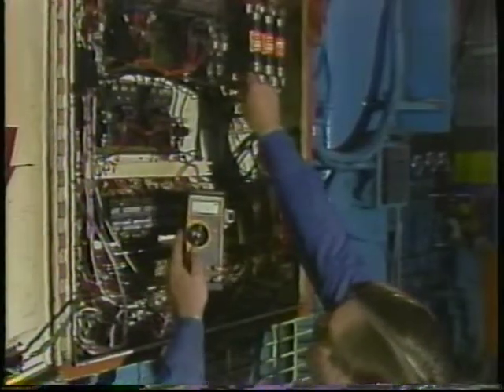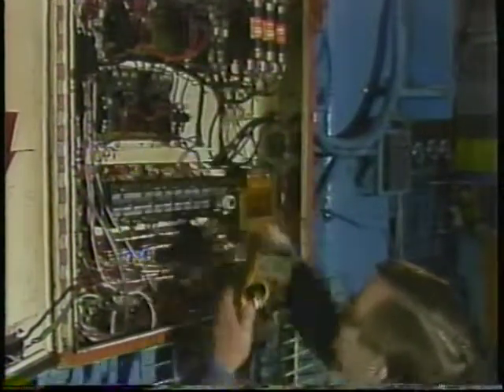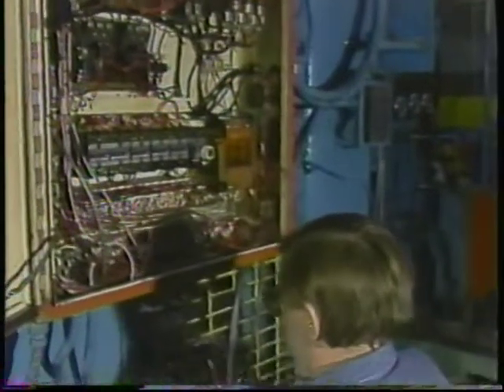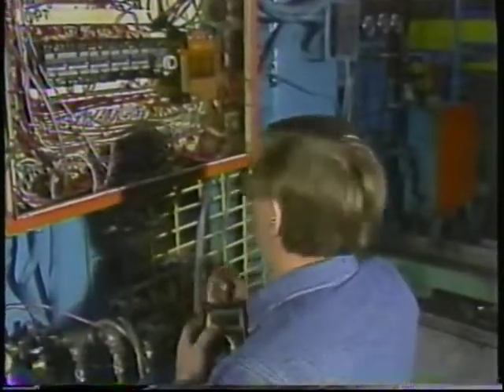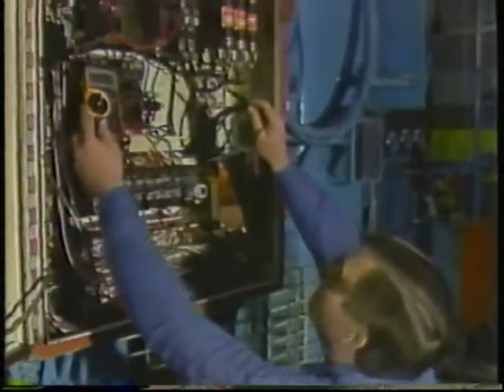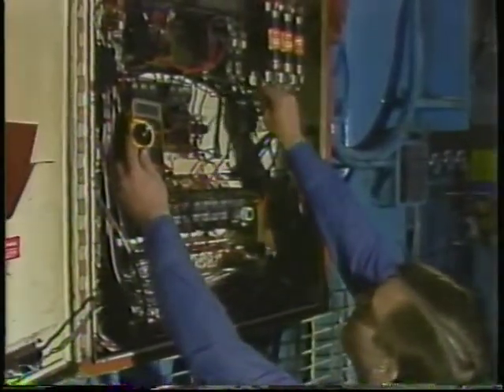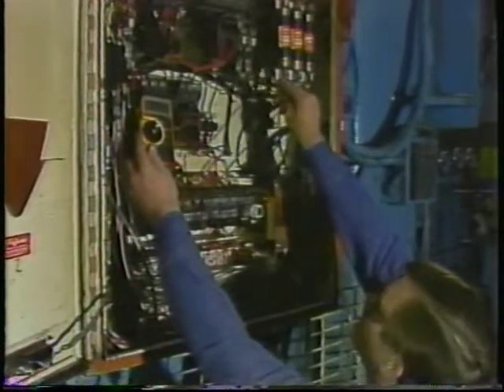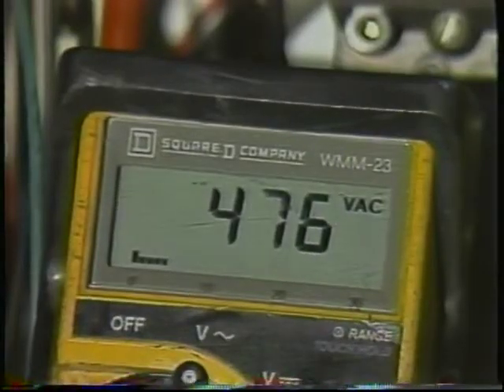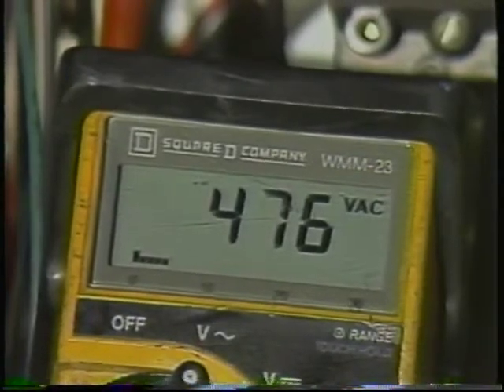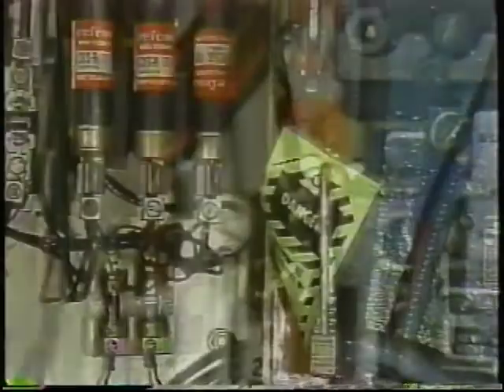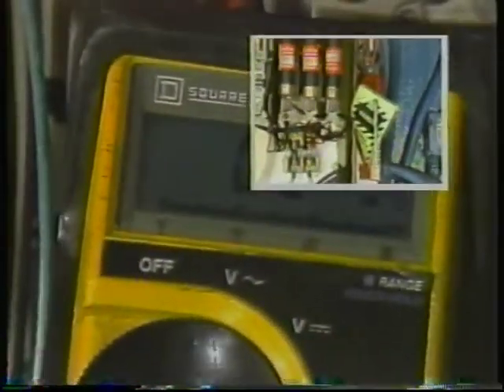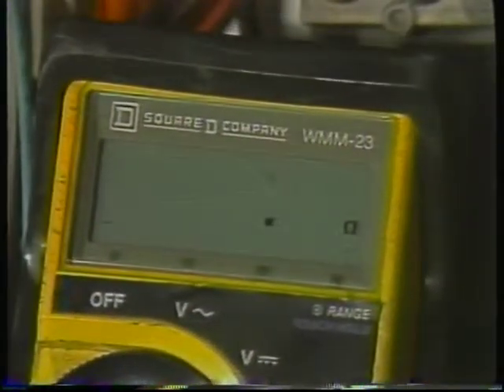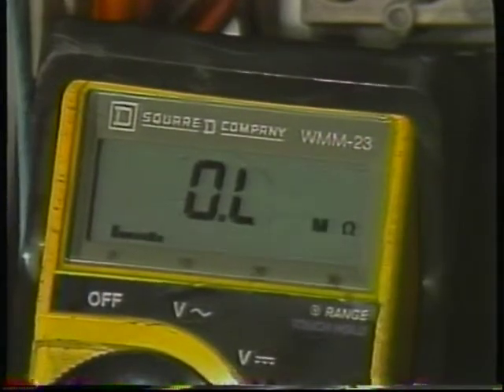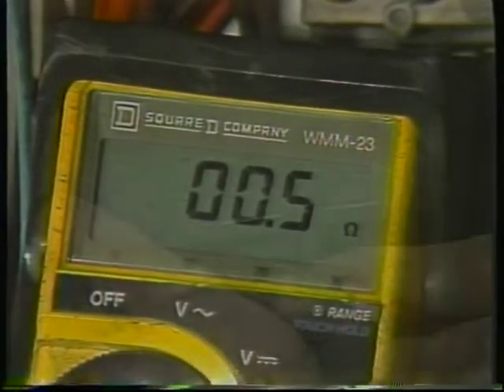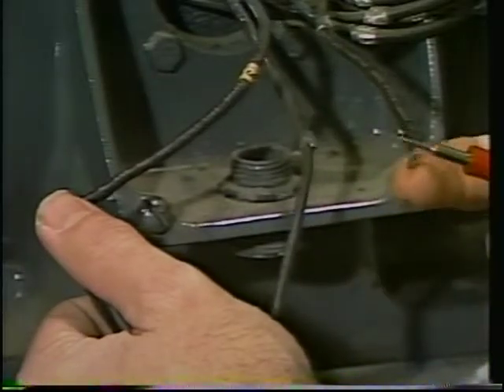The easiest of these probable causes to test for is incorrect voltage. Both high and low voltage can increase motor current. For the motor to run normally, the voltage must be within 10% of the nameplate voltage. Measuring the voltage to the motor at the contactor is adequate in most cases, though it will not detect a voltage drop due to high resistance in the lines to the motor. If measuring voltage at the motor junction box is not safe, you can eliminate a problem in the lines by measuring line-to-line resistance at the contactor and at the junction box. If the readings differ, there is a problem in the lines.